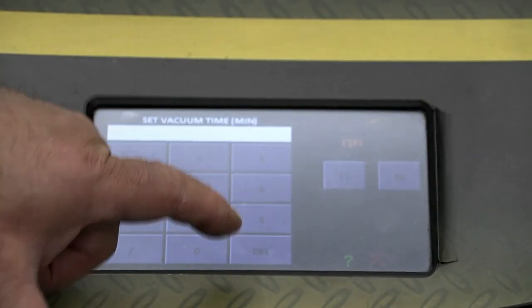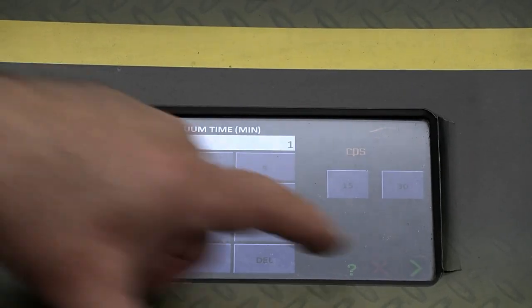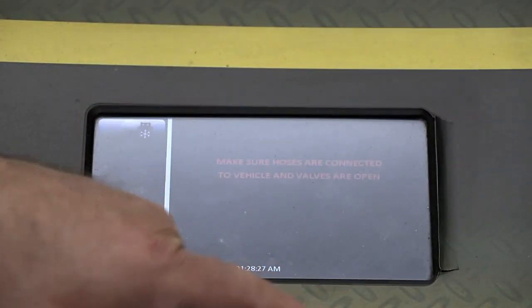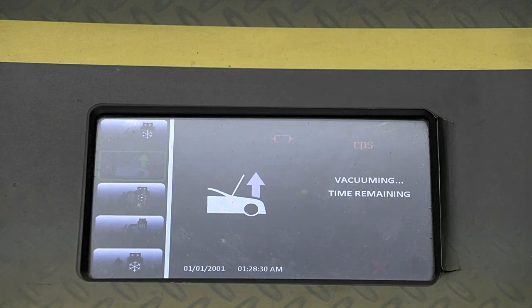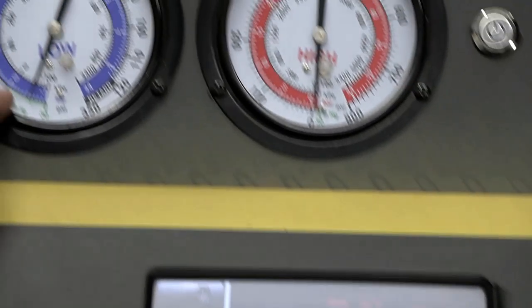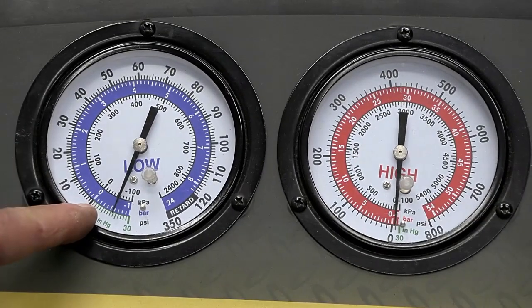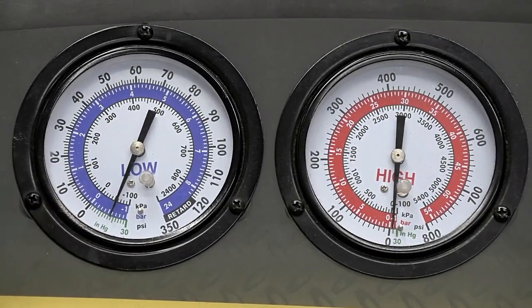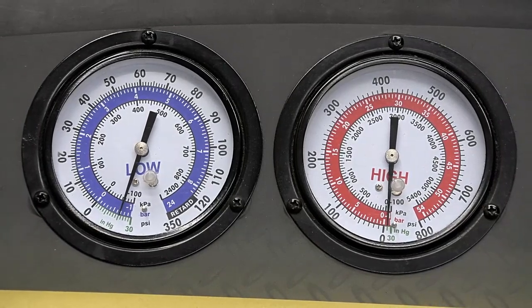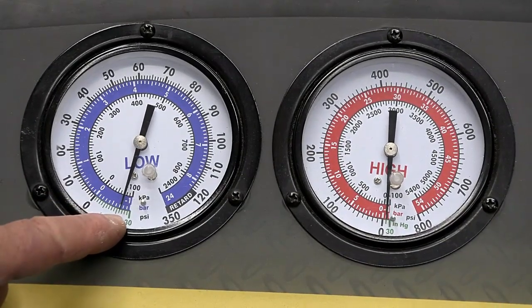That should have gone — I think I waited too long to hit the key. So now it'll pull it down, and if it sees any pressure in the system, it won't allow you to hit vacuum. This should go all the way down to 29.9 or 30.